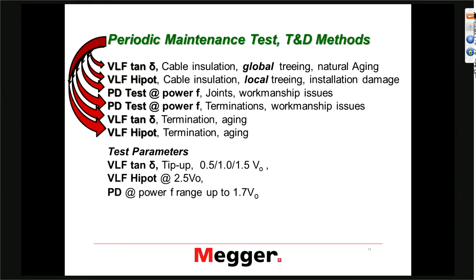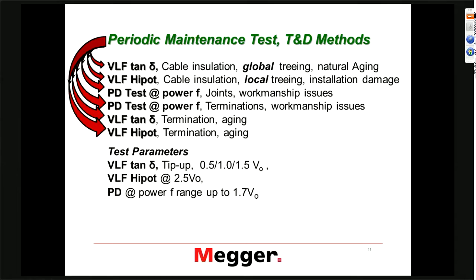By doing a partial discharge test, we can see whether joints or terminations have any workmanship issues, because there is a very simple rule: a brand new splice or termination should have zero PD — as carried out as a field measurement. We're not talking about factory testing here. We have to do these acceptance tests and periodic maintenance tests as field tests, which is a very different environment than what manufacturers can do in their plants.